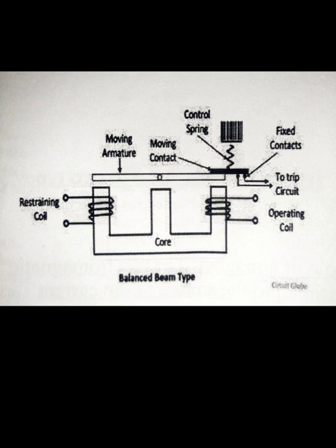The above equation shows that the electromagnetic force consists of two components: one constant, independent of time, and another dependent upon time and pulsating at double the supply frequency. This double supply frequency produces noise and hence damage to the relay contact.